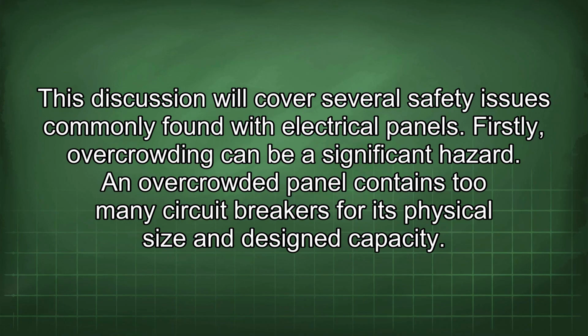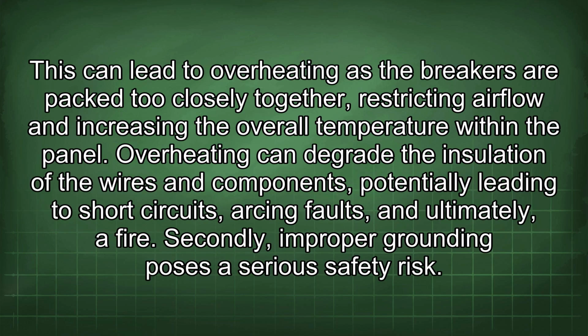This discussion will cover several safety issues commonly found with electrical panels. Firstly, overcrowding can be a significant hazard. An overcrowded panel contains too many circuit breakers for its physical size and design capacity. This can lead to overheating as the breakers are packed too closely together, restricting airflow and increasing the overall temperature within the panel. Overheating can degrade the insulation of the wires and components, potentially leading to short circuits, arcing faults, and ultimately, a fire. Secondly, improper grounding poses a serious safety risk.